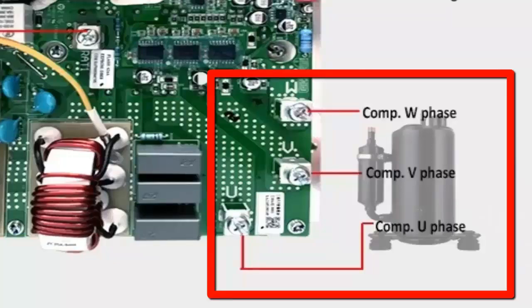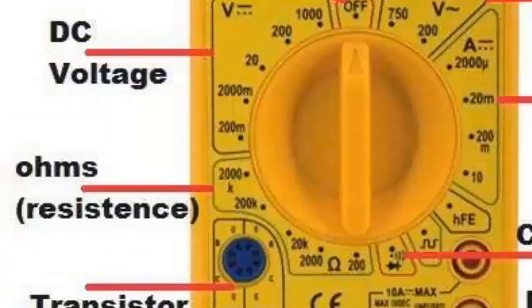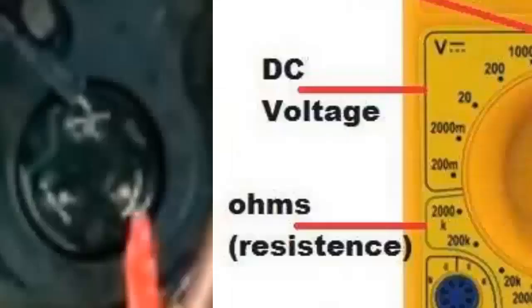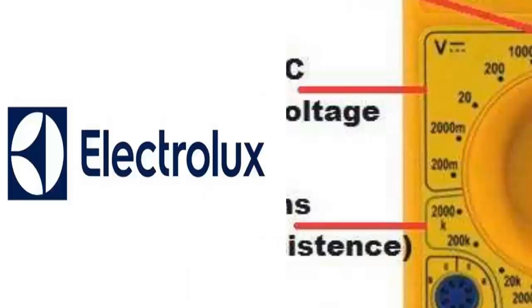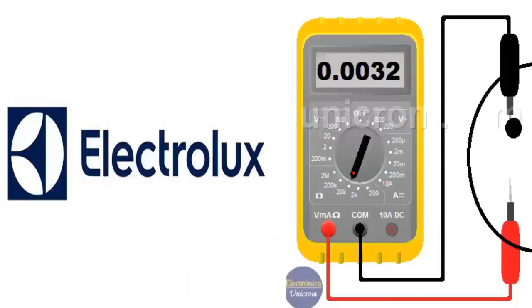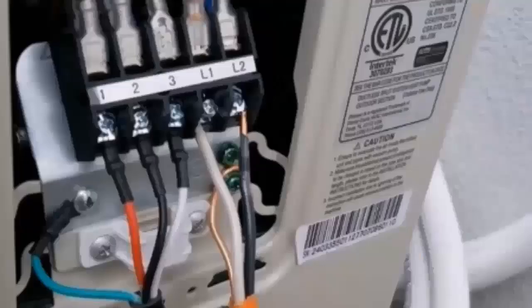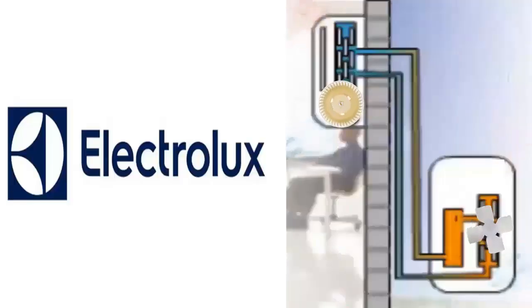You can disconnect the unit from the power and, using a multimeter set to the resistance scale, measure the value of all internal resistances of the compressor motor coils. To do this, measure the values between two energy connection pins on the compressor. All measurements should be equal. Check the electrical connections between the external and internal units for loose points that cause poor electrical contact.